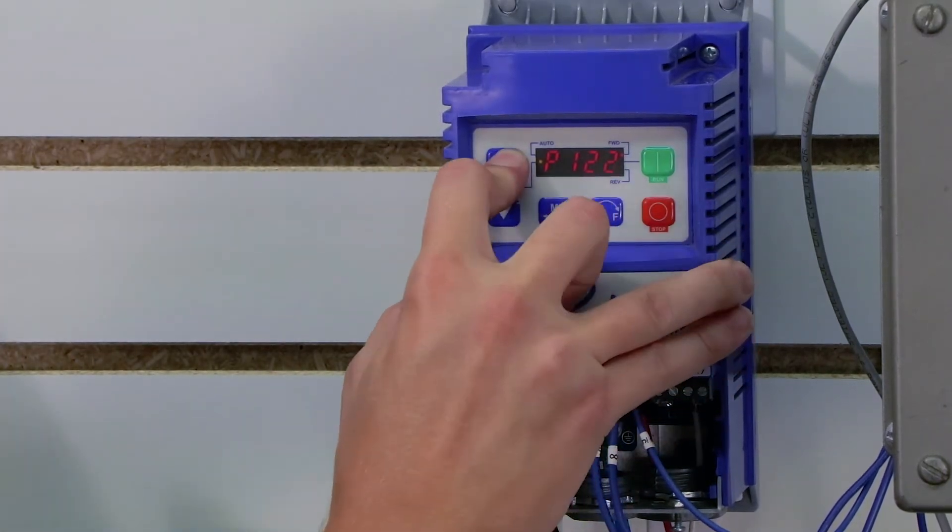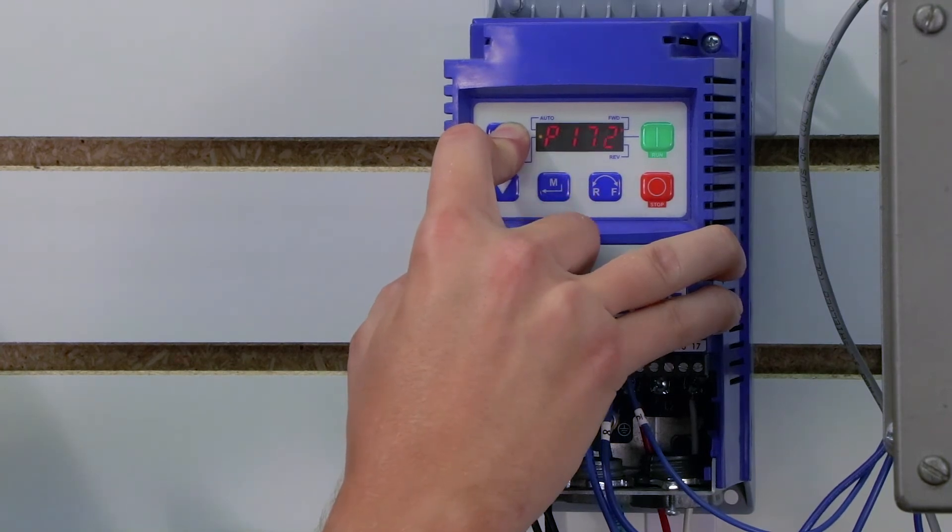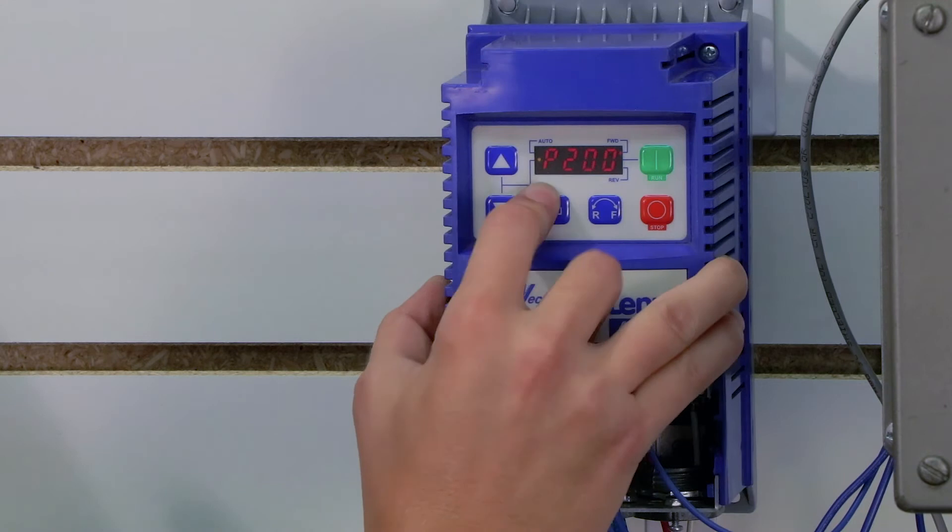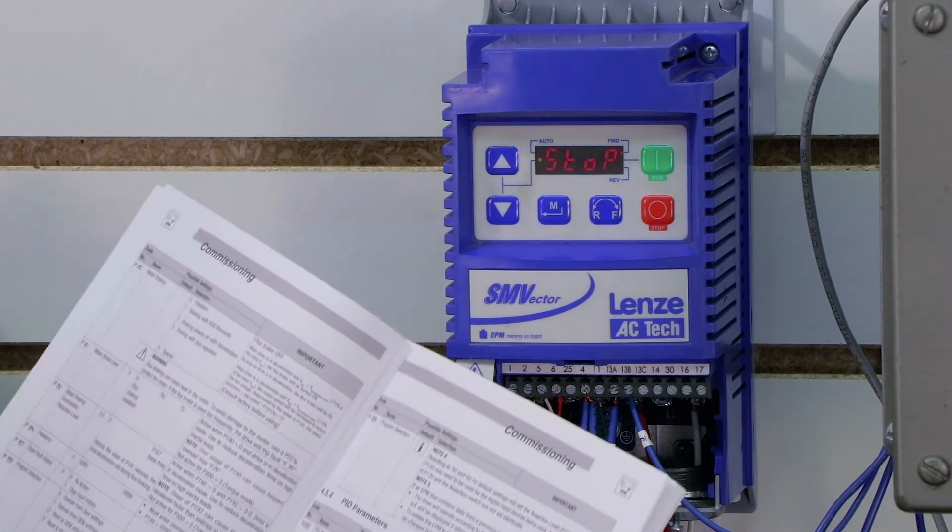So let me go to parameter 200. 200, go up. 200. And we're going to set that to 1. Press Enter. And that turns on PID mode.